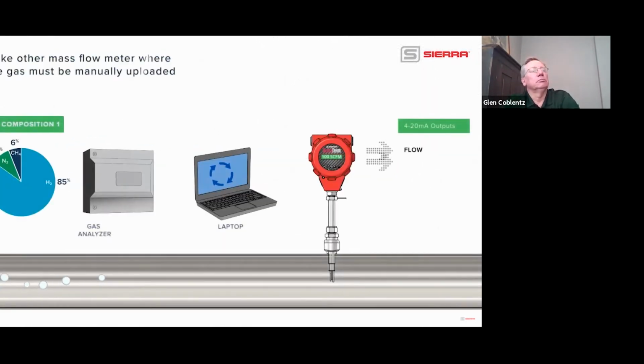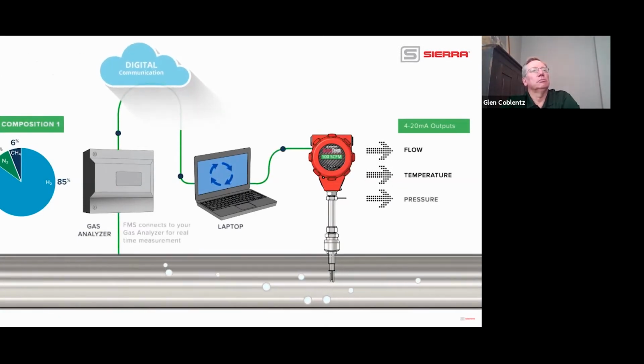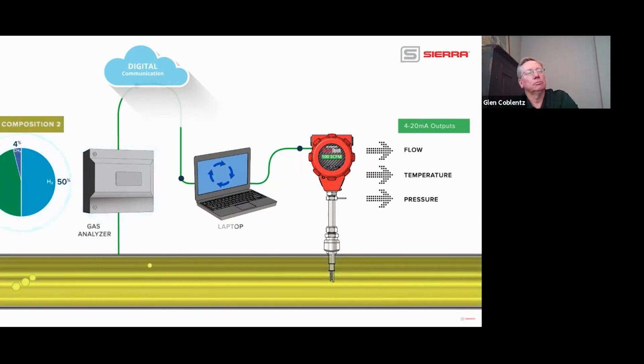Unlike other thermal mass flow meters where flare gas composition must be manually adjusted and uploaded, QMix Real-Time FMS connects to your installed gas analyzer to deliver continuous, real-time flare measurement down to 0.1 feet per second. When the gas composition changes, the QMix Real-Time app loaded onto the supplied laptop reads the outputs from the gas analyzer for an updated flare gas composition. In real time, the app creates a new gas composition and automatically updates the 640i thermal mass flow meter.